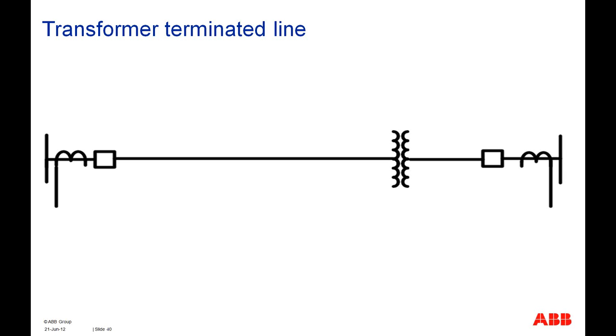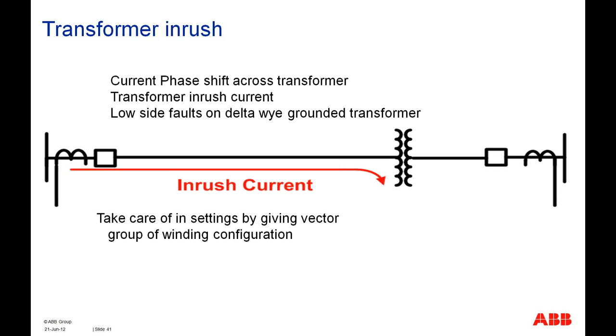Now let's talk about the case when we have a power transformer inside the protection zone of the line differential protection scheme. Because of this transformer, we have to consider certain technical aspects and take care of the transformer specifics. First of all, we need to know about the current phase shift across the transformer. Then we have to take care of the transformer inrush current, because the inrush current will be felt by this CT, but not by this CT. So, to avoid incorrect behavior of the line differential protection, we have to take certain measures to filter out this inrush current.